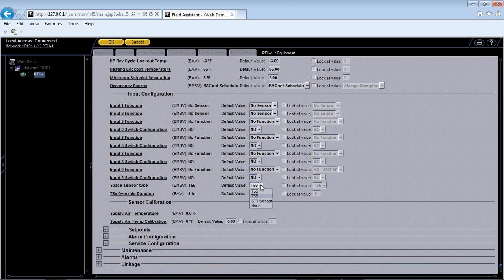So the first option is just a standalone sensor, no display, no set point adjustment, no override, nothing. Okay. The next upgrade from that would be no display on the sensor, but you have a manual override button and a slide bar for adjusting the set point. Again, it wires with just the 4 wires. The third option is a digital display that gives you set point adjustment and manual override, but it also lets you see the space temperature and your set points. And then the final option is only used for unit vents or fan coils where you actually have multiple speeds of a fan. It's a digital display that can let you change set point adjustment, manual override, and it'll also let you bump up your fan speed from low, medium to high.